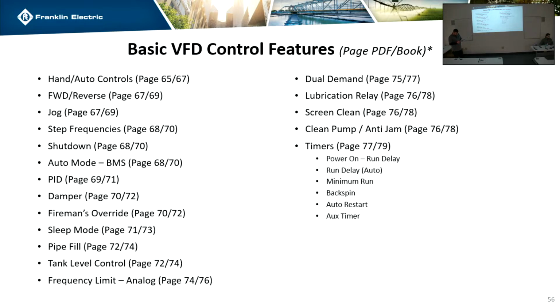So that's just auto mode. So page 70, auto mode, this is what HVAC's going to use most of the time, but this is very kind of straightforward. This is just how to wire or how to set up an auto mode. It's just looking for an auto speed reference. You guys are most likely going to use the ACI or AVI input, and when it's in auto, it's going to say T/C or T/V to let you know that's the mode that it's in. Let's see, feedback.